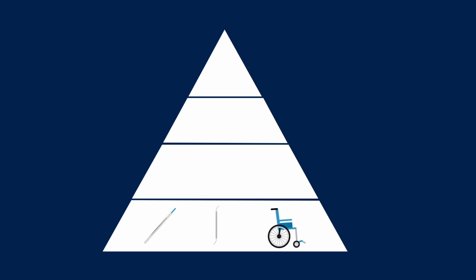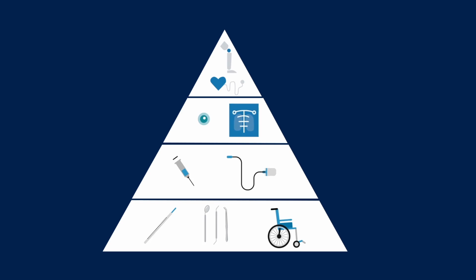Regulatory oversight of medical devices is risk-based. The higher the device's risk classification, the more stringent the requirements to obtain the CE mark, and the more conformity assessment procedures will be sought by the notified body before the device may be sold. There are 4 risk classes for devices within the EU. Class 1 is for low-risk devices. Usually these are non-invasive devices such as tongue depressors or bandages, which are intended for use of under 1 hour.